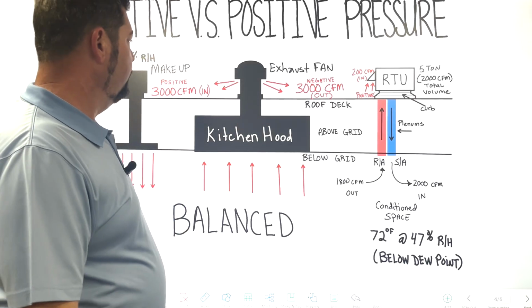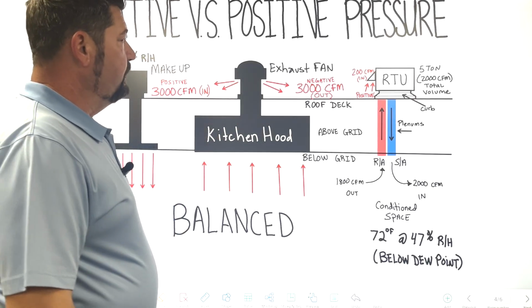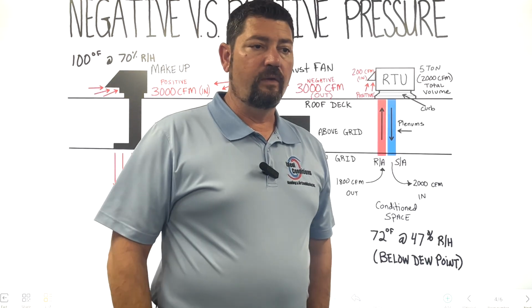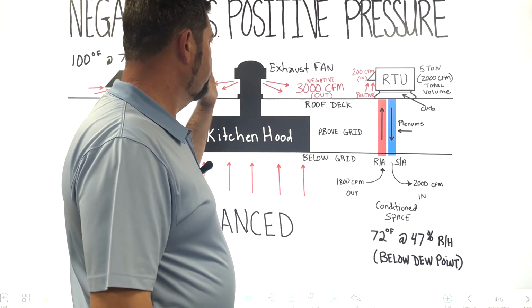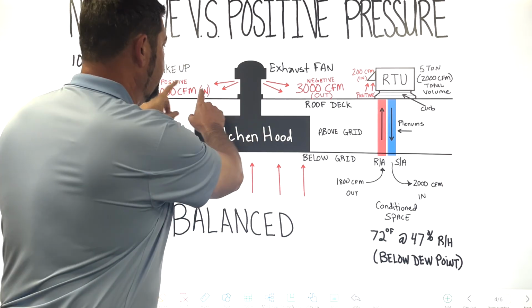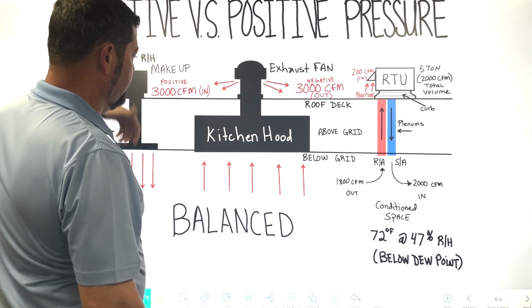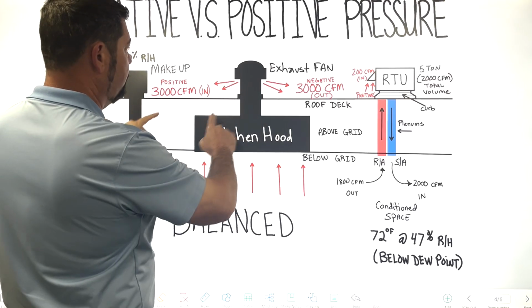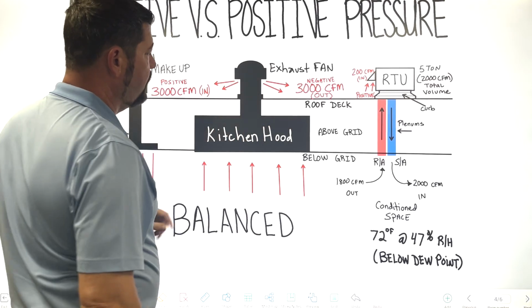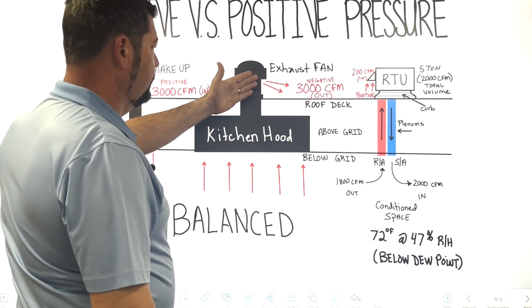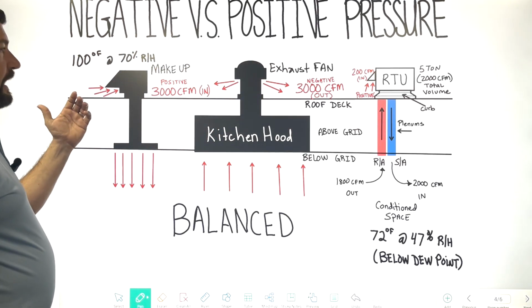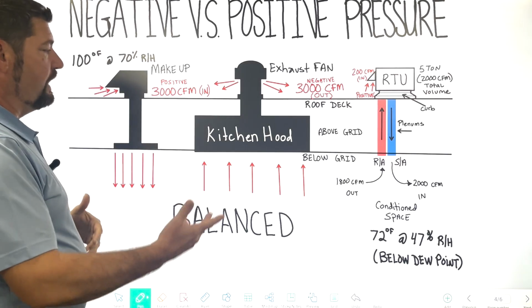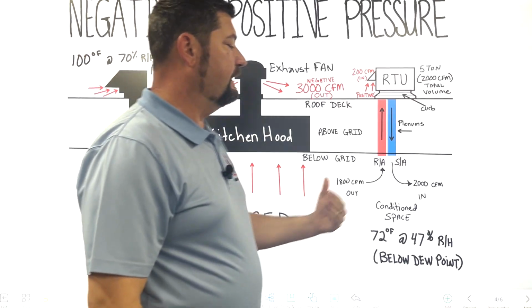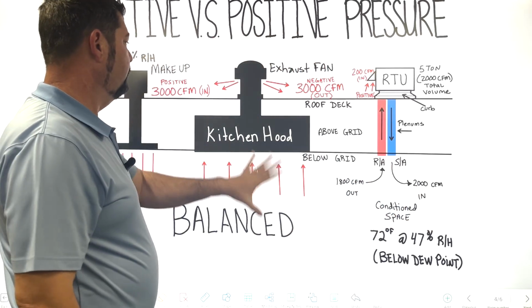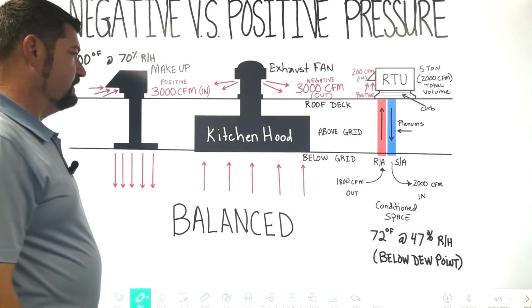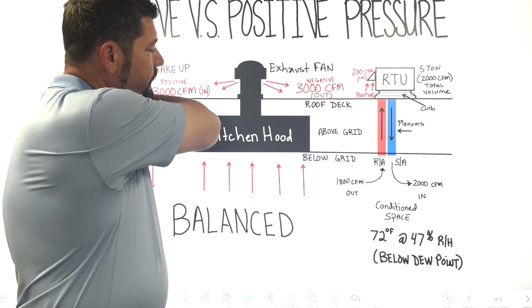A lot of times what happens is people go to put in new exhaust fans because they fail, and they don't match up the RPMs, the horsepower. And so now things that were originally designed to be a combination, specced out so that these numbers are the same, are off. One is now probably 3,000 or 4,000 CFMs, excuse me, and the other one's 1,000 CFMs less. And so now you'll have an imbalance of airflow, creating that negative pressure. And the only way you can fix it is to go back to the source and make sure things are at specs. Common problem, very common problem.